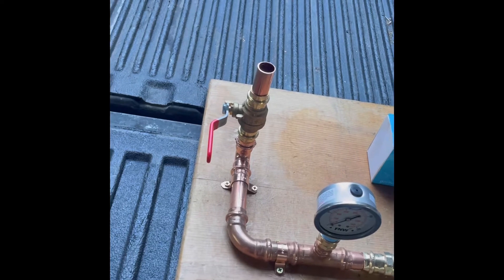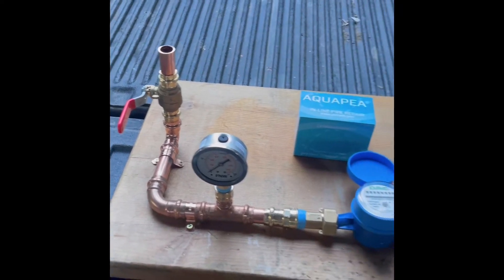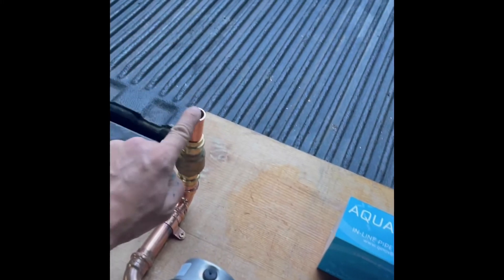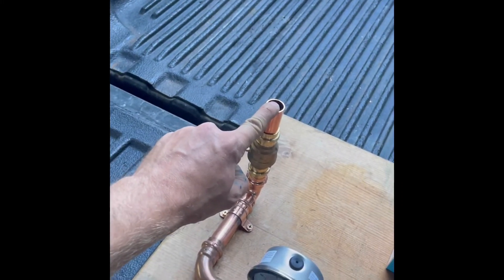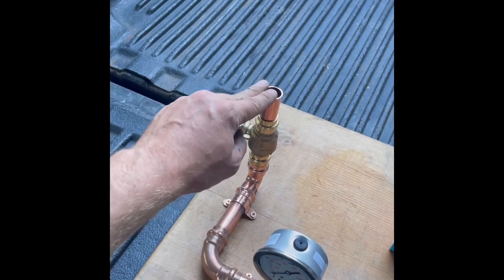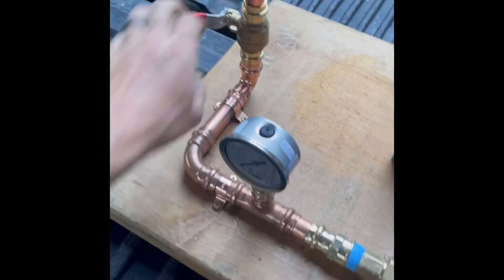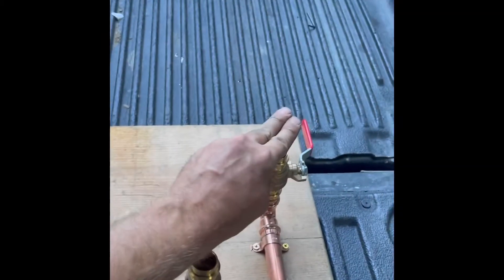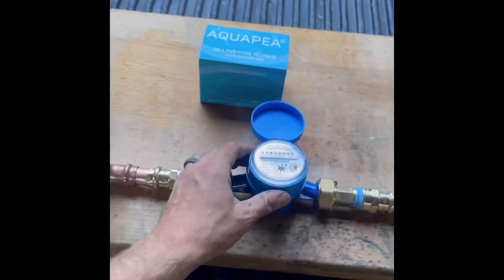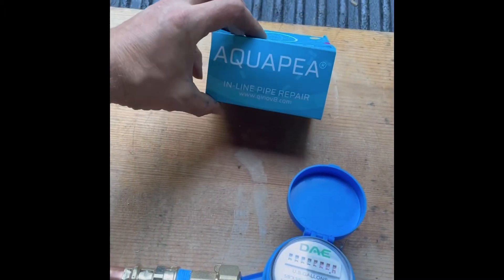The way this works is: let's say you have a leaking line and you've already performed a manifold test to determine which leg of the line is leaking. You would connect this directly to the pressurized side — the incoming water — which you can use PEX, flex hose, SharkBites, whatever works. Use this to regulate the water and detect the pressure. This side is connected to your leaking line. Once both sides are connected, you can determine the flow rate of the leak. There are different sizes of Aquapea for different size leaks.